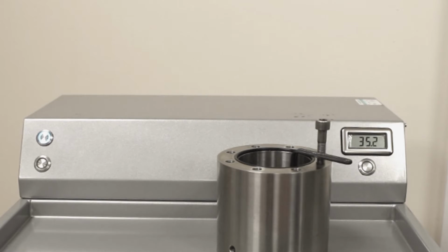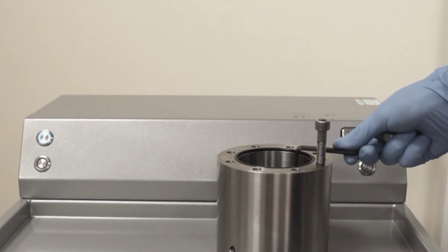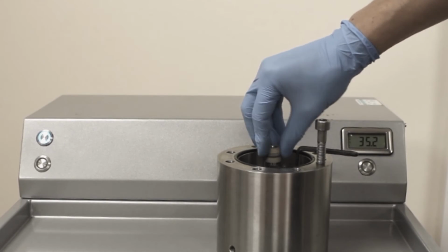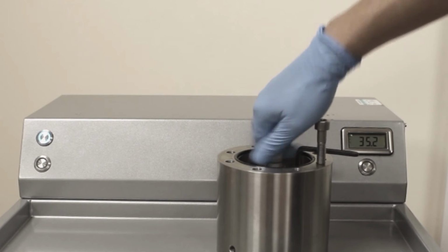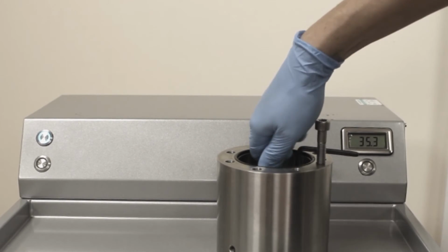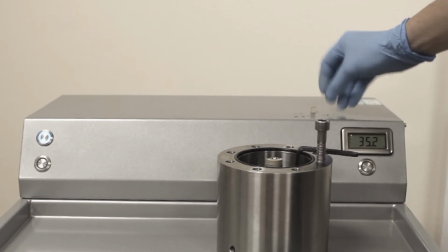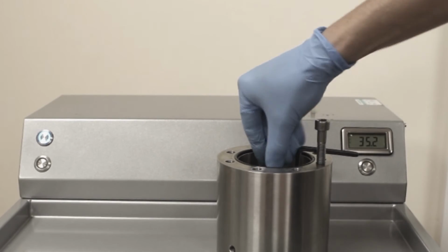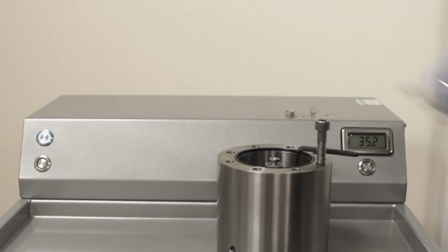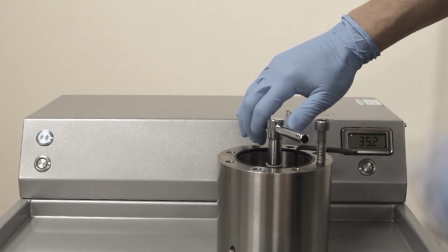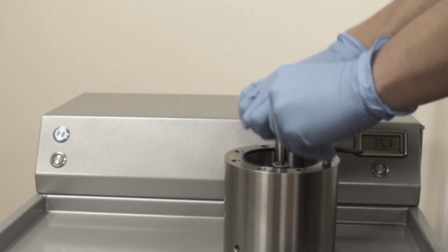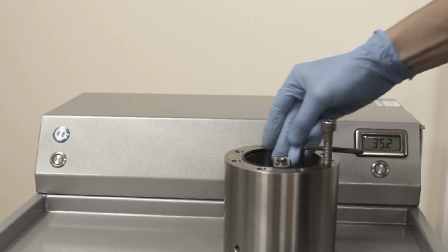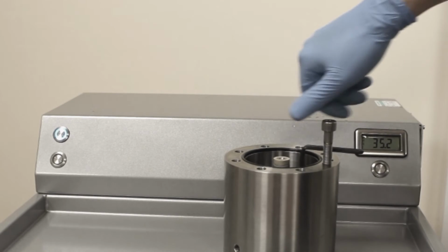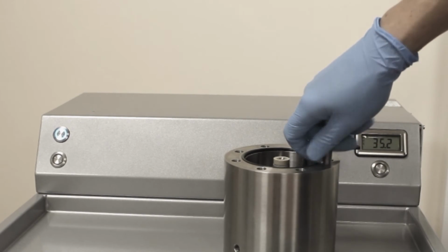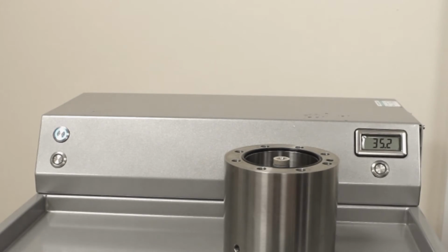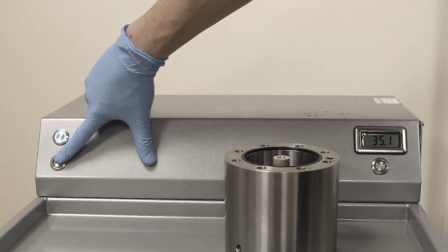To replace the high pressure seal, using one of the bolts from the spacer as a stop, screw the new high pressure seal into the top of the piston, remove the split key caps and tighten using the short 11mm and T-bar. Replace the split caps, remove the bolt and the spanner. Bring the piston to the bottom.